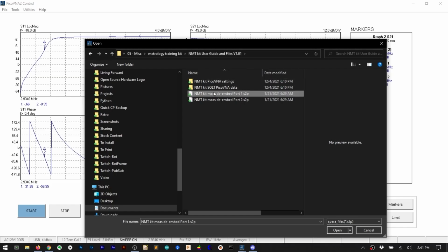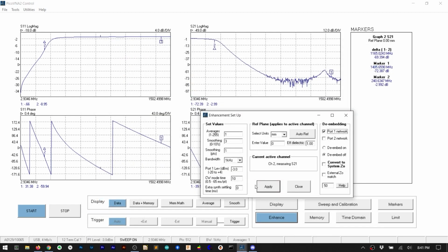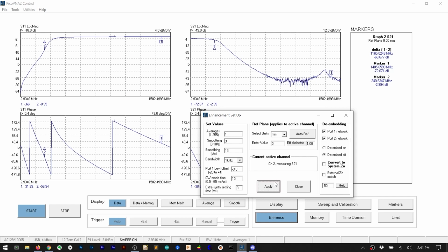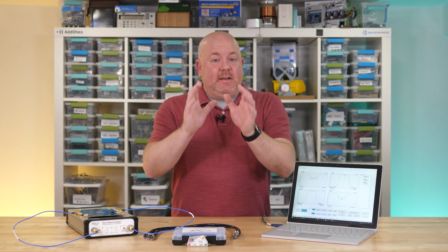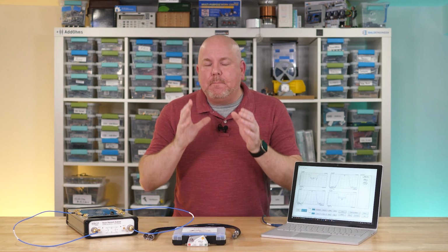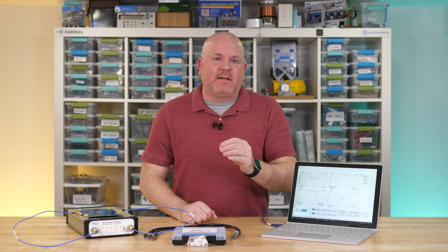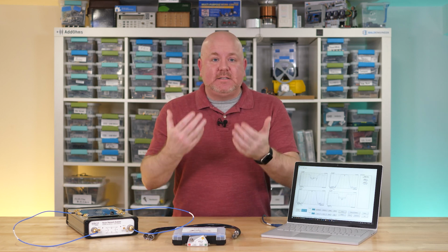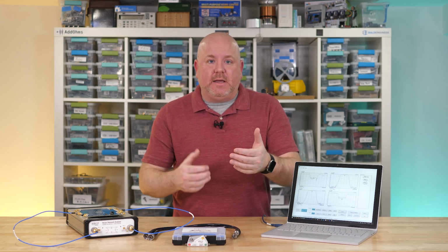Pico Technology provided a generalized S parameter for this PCB design. We can use that to de-embed the trace effects on both port 1 and 2. De-embed is the opposite of embed. What I mean is we are mathematically removing the embedded effects of an element, or in this case, the two PCB traces, which effectively moves our measurement reference plane closer to the DUT.